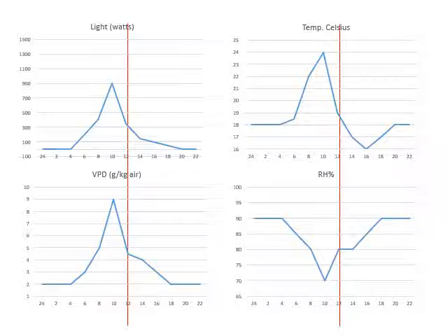Well, at this point, the clouds came in. Most likely the boiler should have kicked in to maintain the temperature in the greenhouse instead of letting it dip and then turning the boilers on and recovering late in the day. So here we have a situation where we were too slow to react from the climate, and not to mention we started the day with high humidity, so we probably should have had the vents on and some heat on, or maintained a warmer temperature, although 18 degrees is not that bad for overnight.